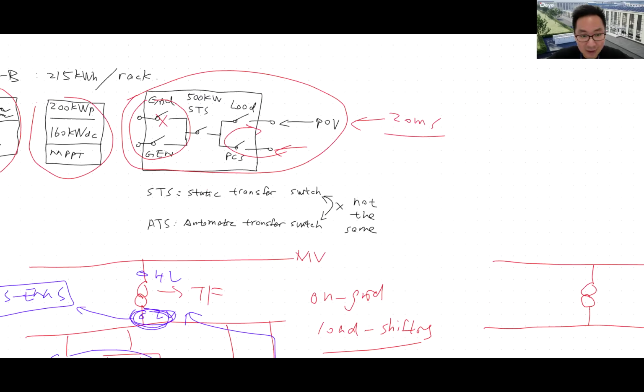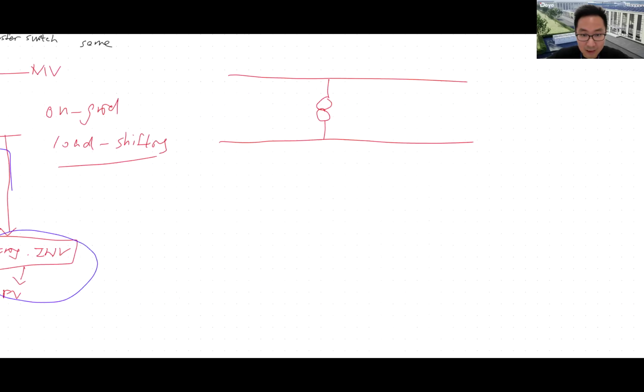But ATS works on a completely different strategy. It's like a time delay switch. When the grid goes out, the ATS will try to reclose the breaker a couple of times until the generator has started or something. So that's just different terminology, I'm just getting that clear. That could be our STS module or cabinet, up to you. The STS cabinet is slightly more expensive. The STS module is cheaper, but will take up more space in your electric room.